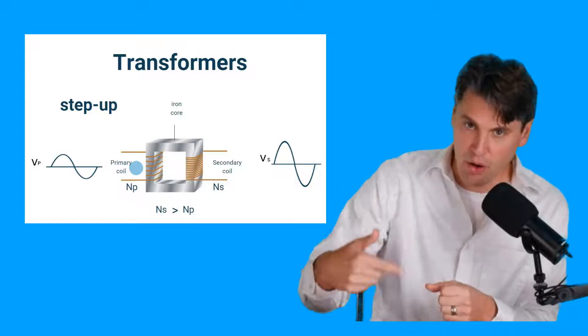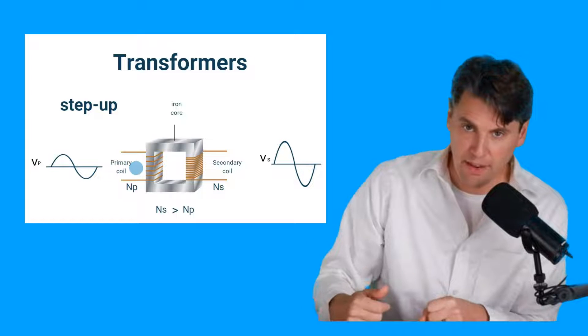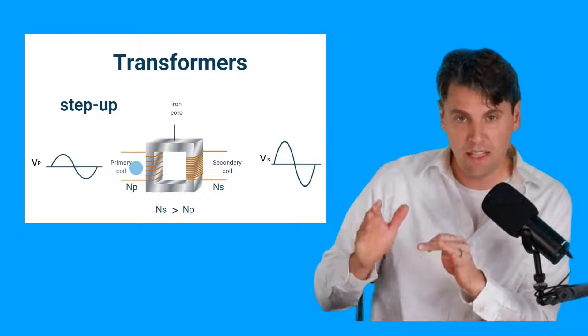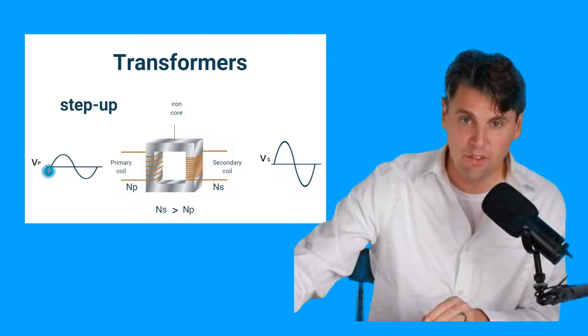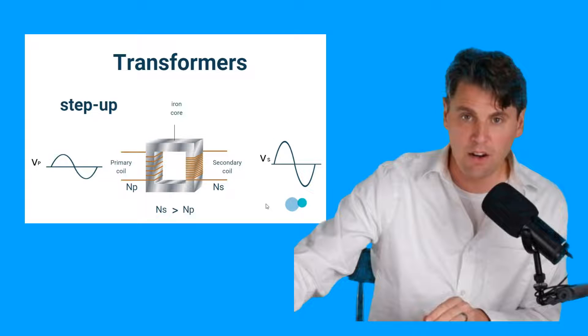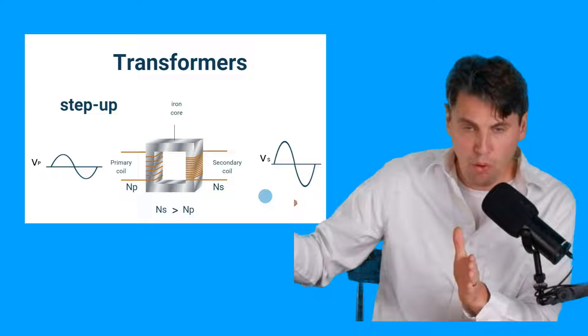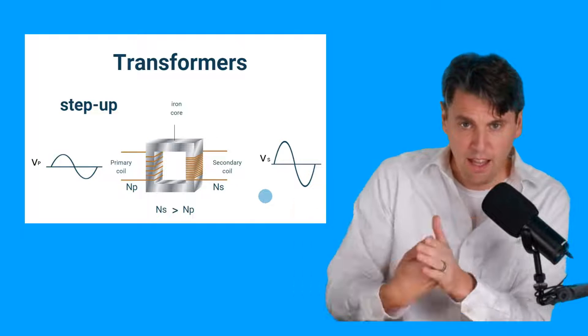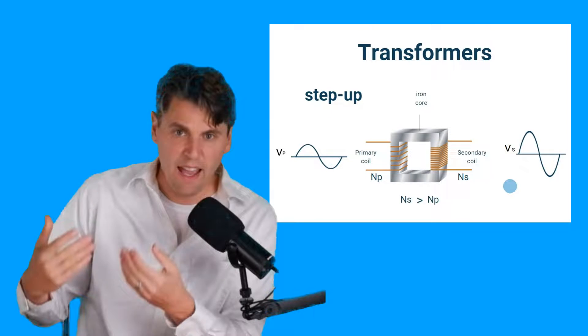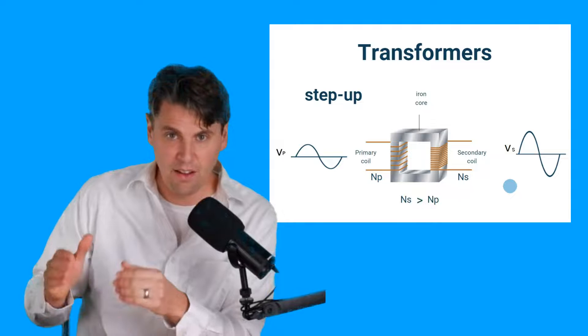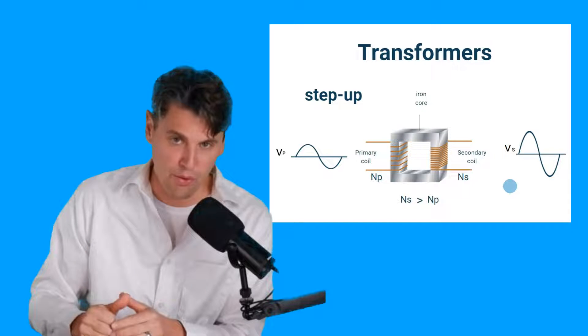By changing the ratio, the number of coils we have on each side, we can actually change what the signal is going to look like in terms of the voltage and in terms of the current. What we care a lot about on our x-ray circuit is we want to be able to pull electrons across, hit them hard into a heavy metal, and we need tens of thousands of volts in order to do that.